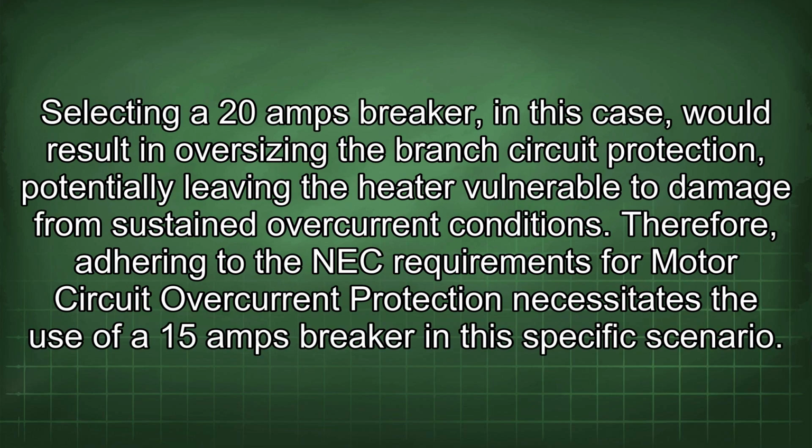Selecting a 20 amps breaker, in this case, would result in oversizing the branch circuit protection, potentially leaving the heater vulnerable to damage from sustained overcurrent conditions. Therefore, adhering to the NEC requirements for motor circuit overcurrent protection necessitates the use of a 15 amps breaker in this specific scenario.